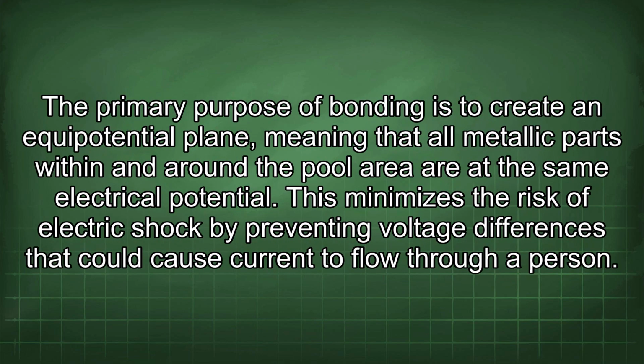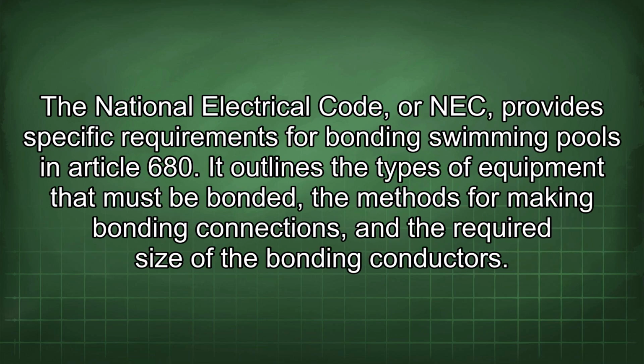The primary purpose of bonding is to create an equipotential plane, meaning that all metallic parts within and around the pool area are at the same electrical potential. This minimizes the risk of electric shock by preventing voltage differences that could cause current to flow through a person. The National Electrical Code, or NEC, provides specific requirements for bonding swimming pools in Article 680. It outlines the types of equipment that must be bonded, the methods for making bonding connections, and the required size of the bonding conductors.